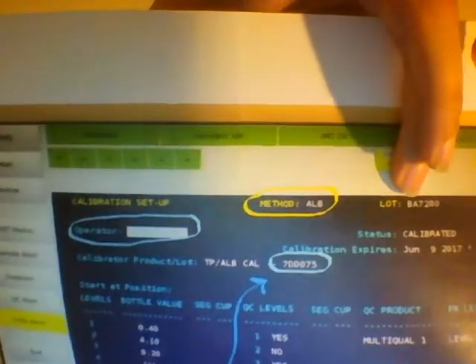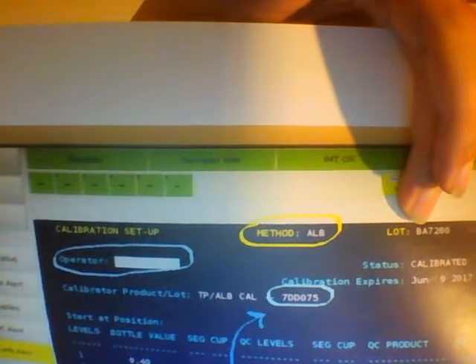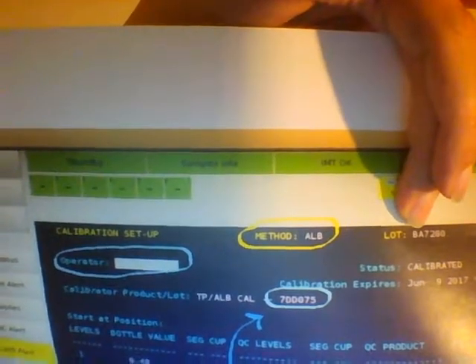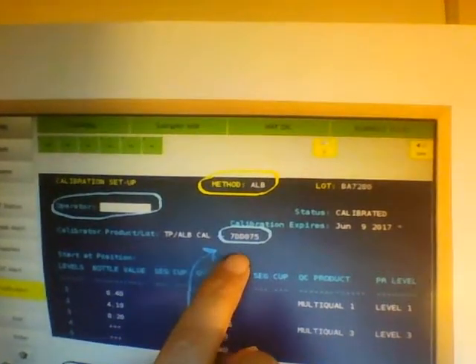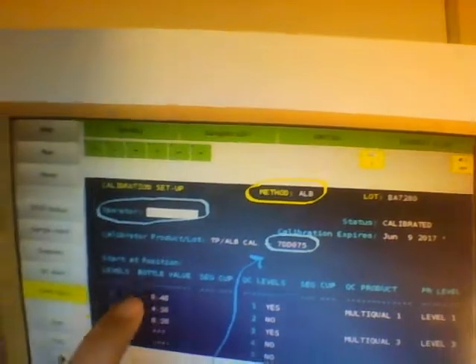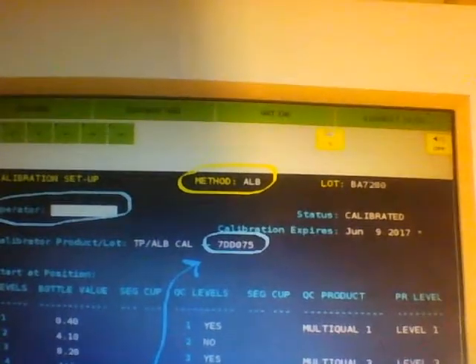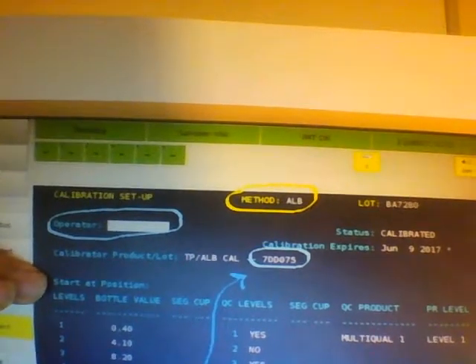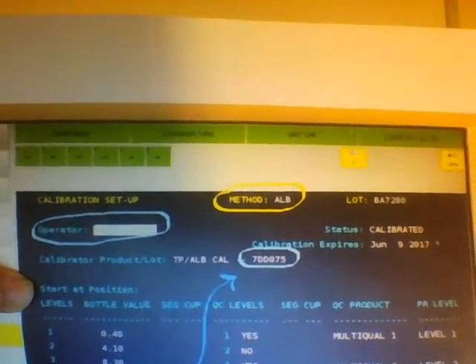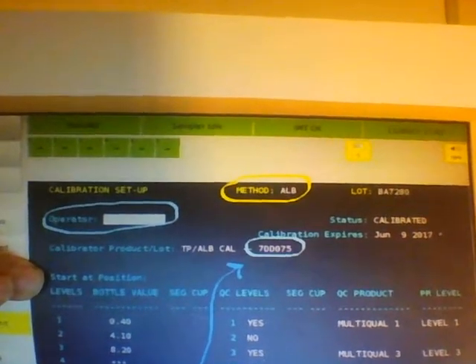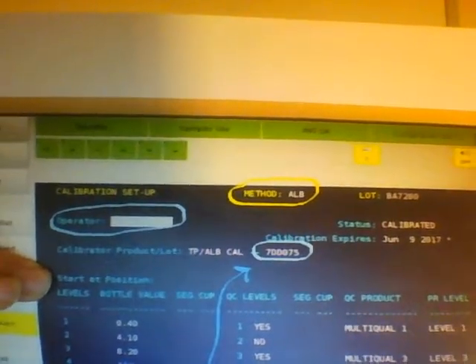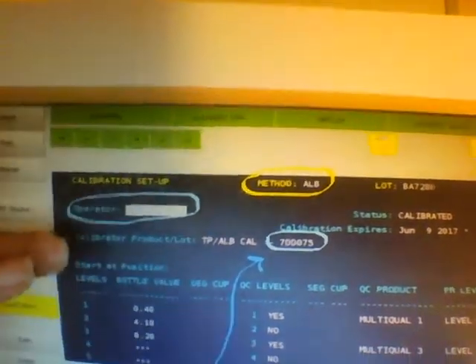For your lot number, make sure that the reagent you're calibrating matches the lot that's up here. For your calibrator, make sure that the calibrator you have matches. This is kind of a final check. Put your initials in the operator ID, and enter the start position right here from whichever rack you choose. If you chose rack C, you'd put position C1. If you chose rack A, you'd put position A1.